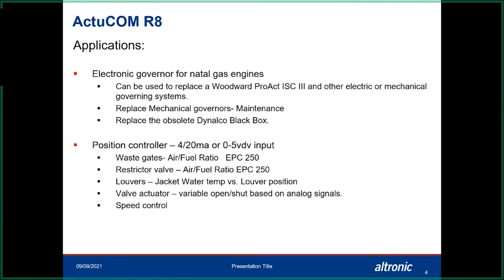So like I said, we'll typically replace regular old mechanical governors, your Woodward UG8s and stuff like that. And why would we really want to replace those things? I mean, they've been out there for 50, 60 years, but we're starting to run into more environmental issues with the leaking hydraulic fluids and stuff. Our world's turning more to electronic control. With the Woodward UG8, you'd have to put maybe an air actuator type head on it to be able to control the speed with it. And with doing that, that's additional tubing. It's a device, an I to P or something, to send pressure signals to those governors to be able to vary the speed. Well, with the electronic governor like the ActuCOM, we can eliminate nearly all of that stuff. We can eliminate the linkage. We eliminate tubing for pressure, whether it's gas or air.